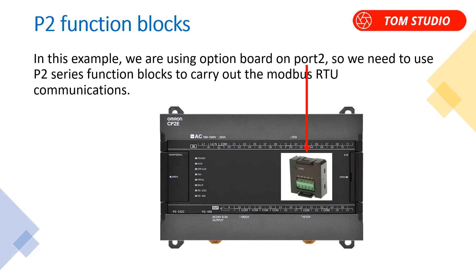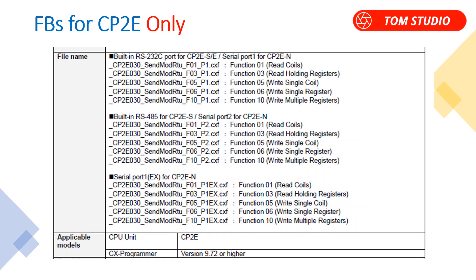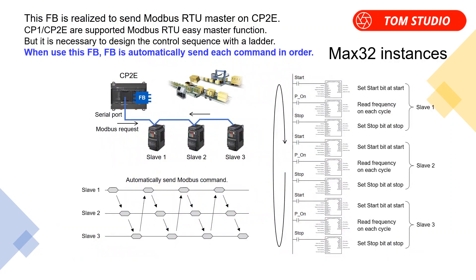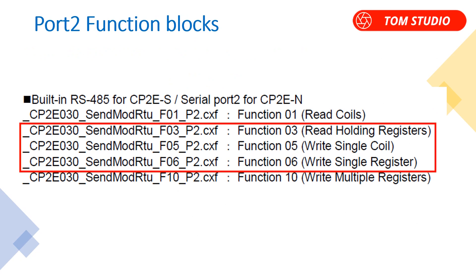All of these function blocks are purely designed for CP2e series PLCs — you cannot use them in CP1L, CP1E, CP1H, and so on. In the past, implementing Modbus serial communications required designing a control sequence inside the PLC program. The new CP2e Modbus function blocks no longer require extra code for command sequence control — they automatically send and receive Modbus commands. In this example, we are using function 3, 5, and 6 — three different function blocks to control and monitor the 3G3 MX2 VSD.